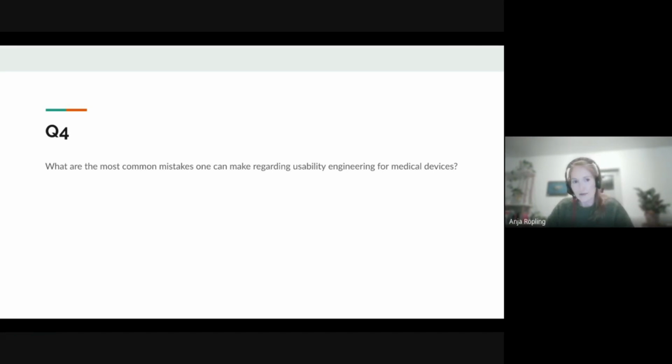And then the rest of the mistakes, I would say, are also a lot content driven. So how you set up your usability tests, also how you describe your use scenarios, because what's often done is just writing scenarios which are more driven from the GUI perspective, so that you end up testing every single feature, every single button in the GUI, instead of really focusing on the task the user wants to do with your device and the goal which they want to reach, and showing that they can do that safely by using your features. So it's just the other way around that I would do it. So I would say maybe those are at least two of my top problems that I see a lot.